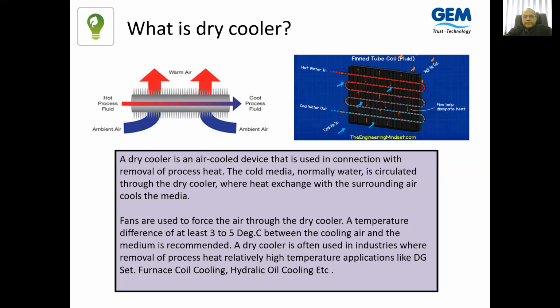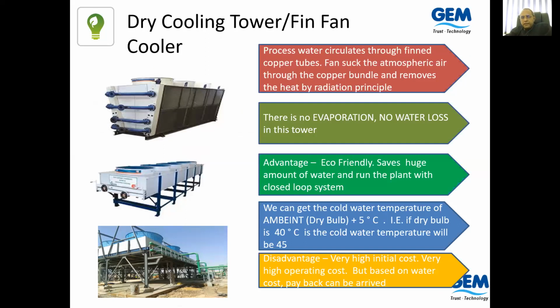Dry cooling is nothing but using ambient air to cool the water. The only disadvantage of this process is that the temperature you can achieve is only ambient plus 2 to 3 degrees. So this is what we can achieve with a dry cooler. It is normally used only for oil cooling or some specific applications where your water inlet temperature to the process can be 40 or 45 and above.